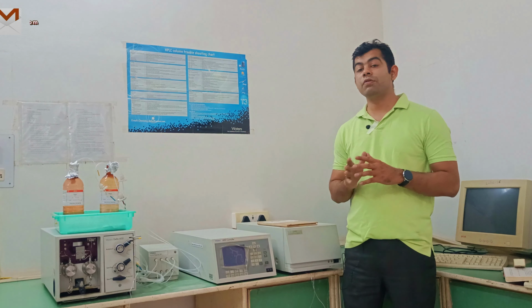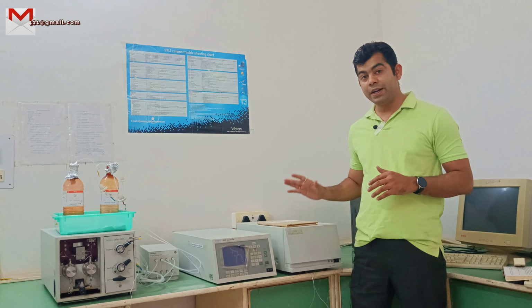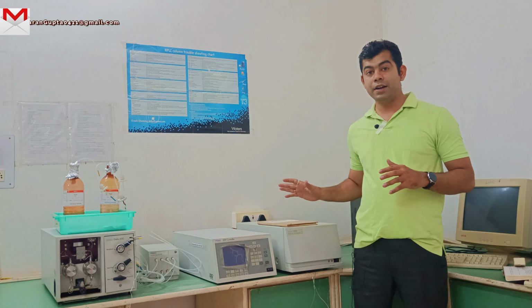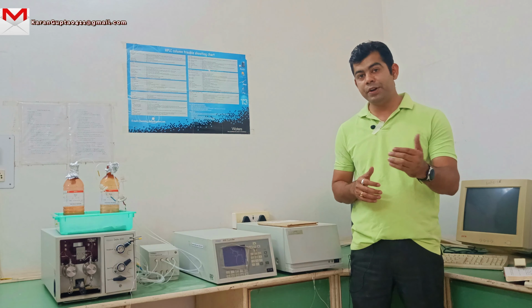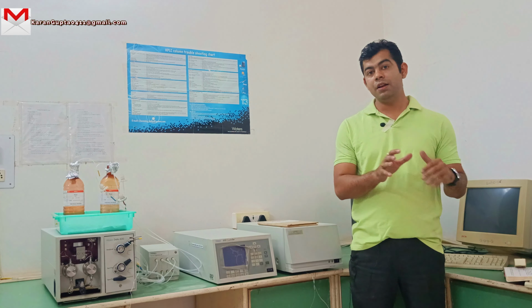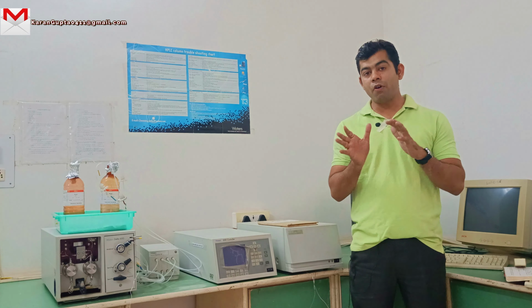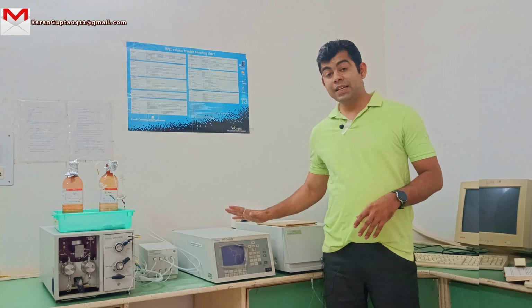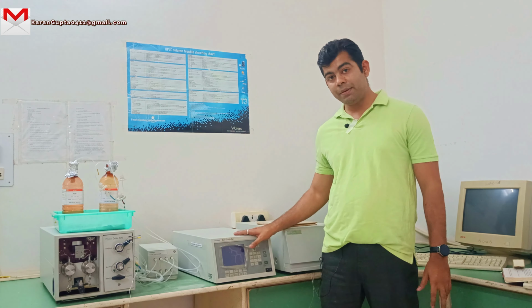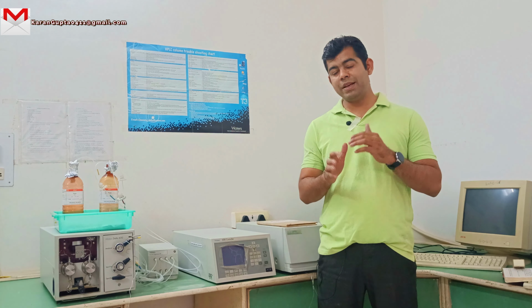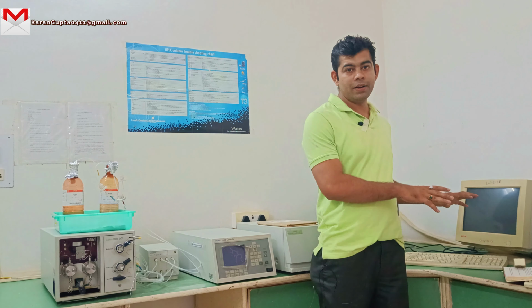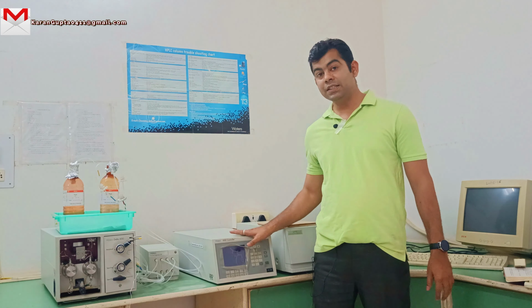So it is one of the most important parts of HPLC, called the detector, and I have a photodiode array detector. I will make a separate video about detectors and their principles when I explain the principles of all detectors. This information helps you most in a quality control laboratory. This is a controller. If you want to operate our HPLC manually, you use this type of controller. Basically all HPLCs are controlled by software, but several times we do not use our HPLC via software, we use it directly and manually. That's why this controller is used.